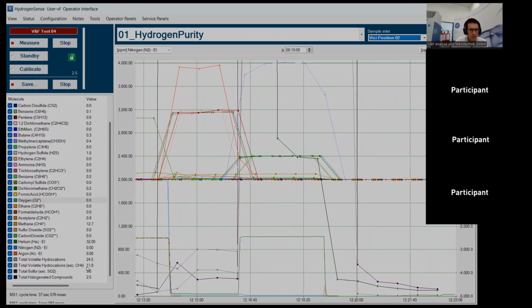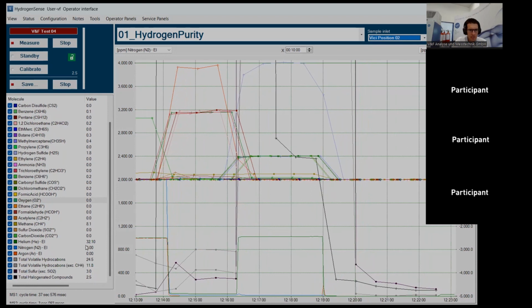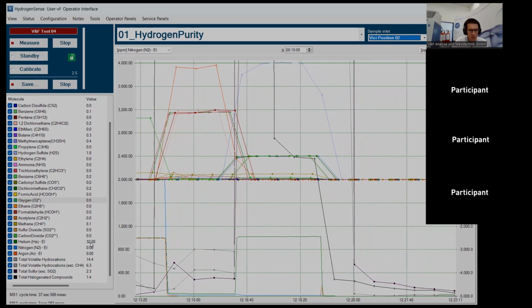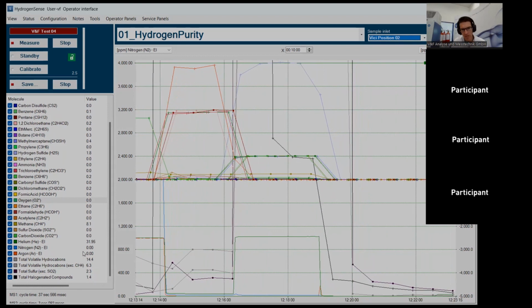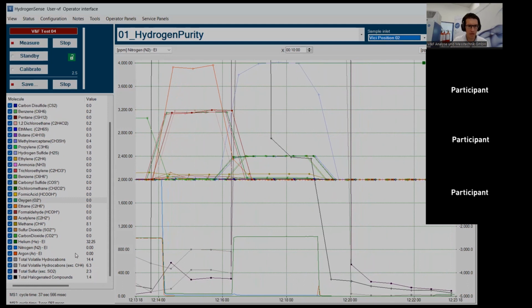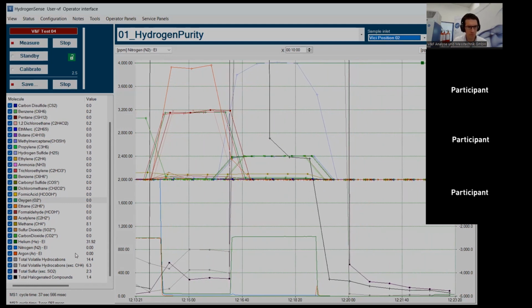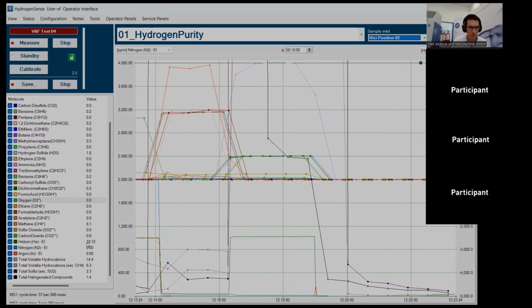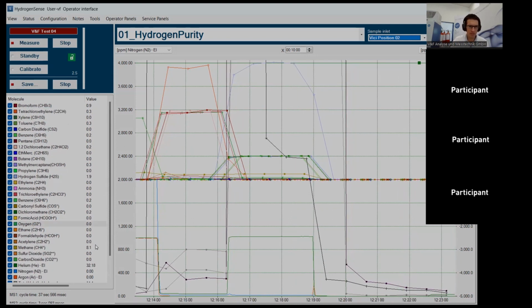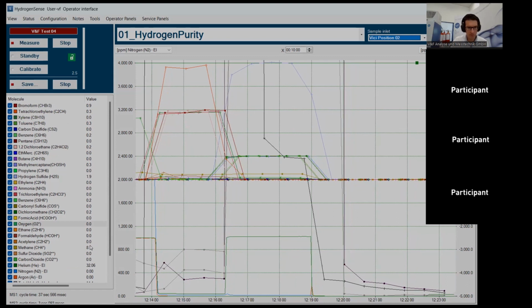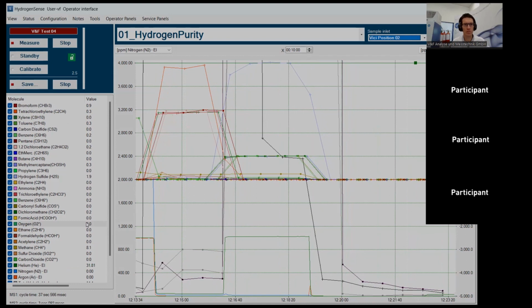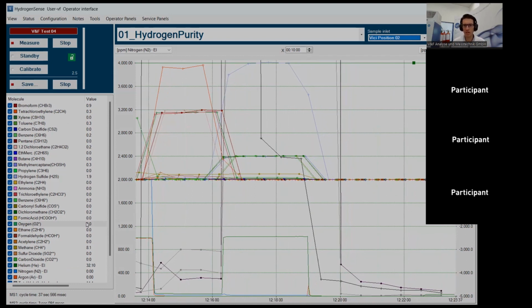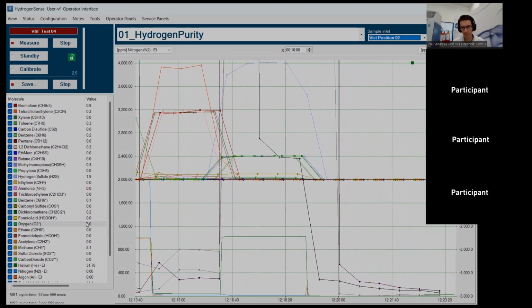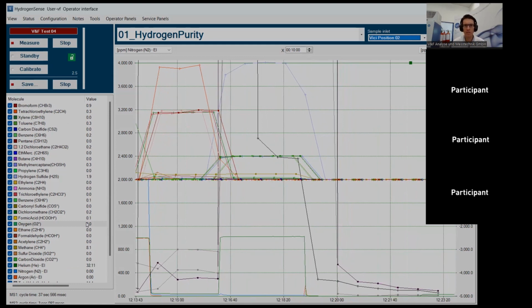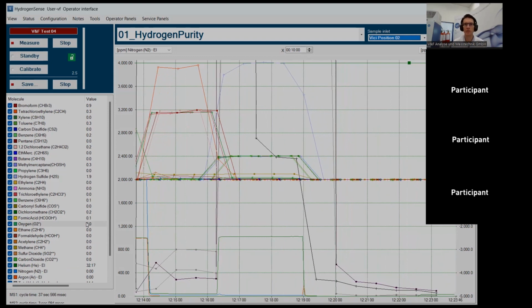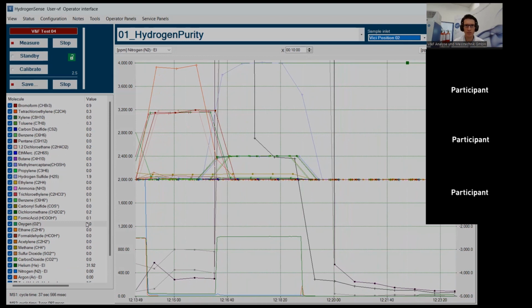And so we see here, I chose this gas in specifically because I know that this hydrogen 5.0 has a little bit of excess helium inside. This pretty much comes from the way it has been produced. So it's probably a steam reformed type of hydrogen, which tends to contain a little bit more helium. And we can then have a look at the acquired data and do a brief evaluation in order to see how the final measurement results will be or can be computed. So this is the really basic manual way to do that. But of course, with the fully automated solution, this is something that can be easily done in a fully automated way.